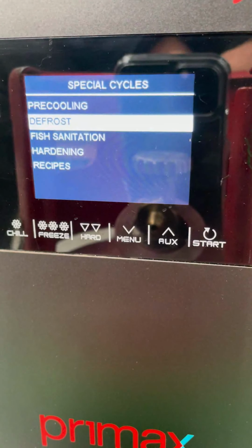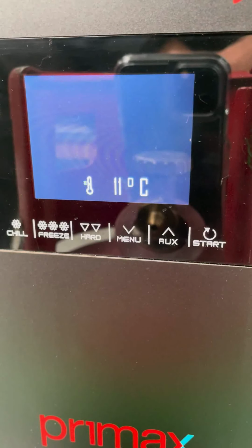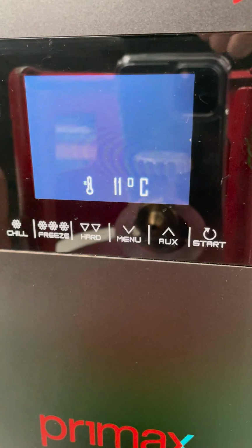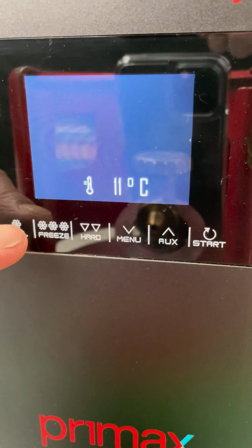How? You need to open the door, the machine will start the ventilation without switching on the cooling system. So the melting of the frost, of the ice inside the cavity, will be done by air from the environment, which will be sucked in by the fan, turning at the highest possible speed with the door open. The preset is 30 minutes, but you can stop the cycle before time, or you can increase that time. Simply arrow up, arrow down. So after defrosting, the machine will be clean and ready for different cycles.